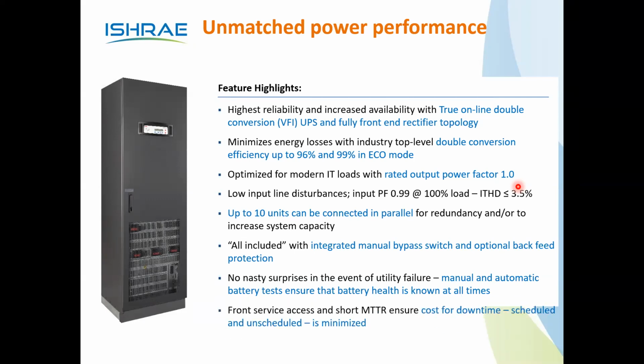And front service access. Space is now the main constraint. In unity output power factor UPS systems, all the critical components, be it semiconductors, fuses or breakers, whatever it is, are placed on the front side of the UPS. So if we are going for multiple UPS systems, we don't need to consider additional space at the rear side.